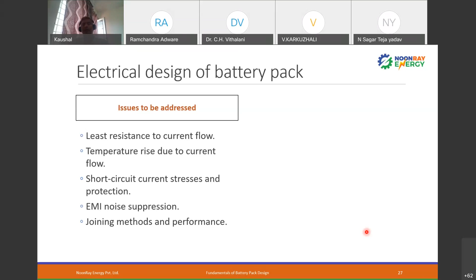What becomes most important in electrical design is the bus bar. An improperly designed bus bar can impair system operation. It will not give you sufficient current when you require it, or it will heat up. Once it is heated up, you are losing energy. That would result in poor efficiency. It overheats itself and nearby components. Not only does it heat itself, it will heat the cell also. It will heat the other components nearby.